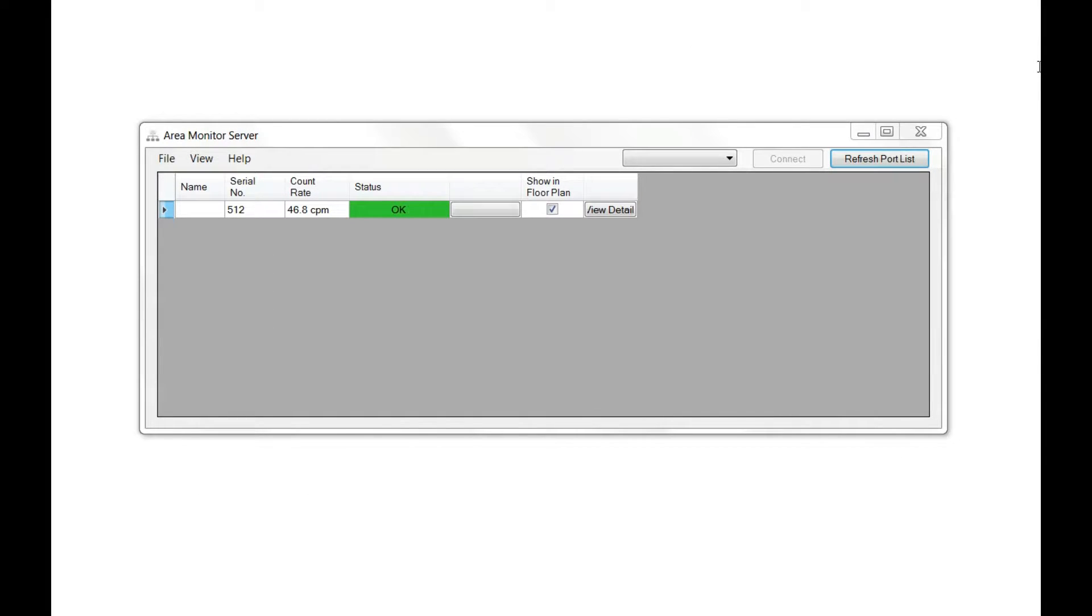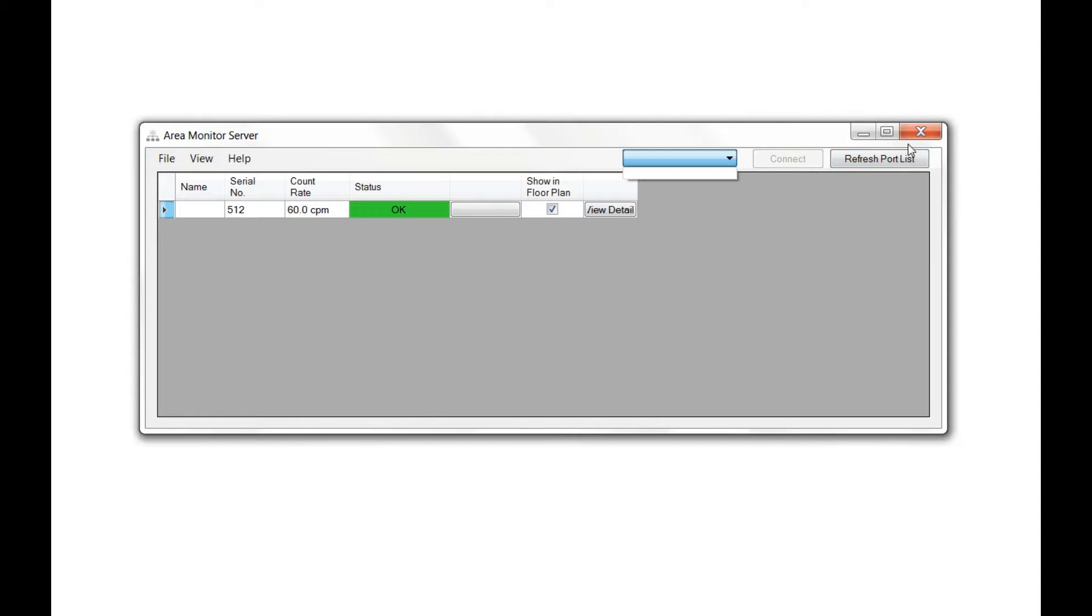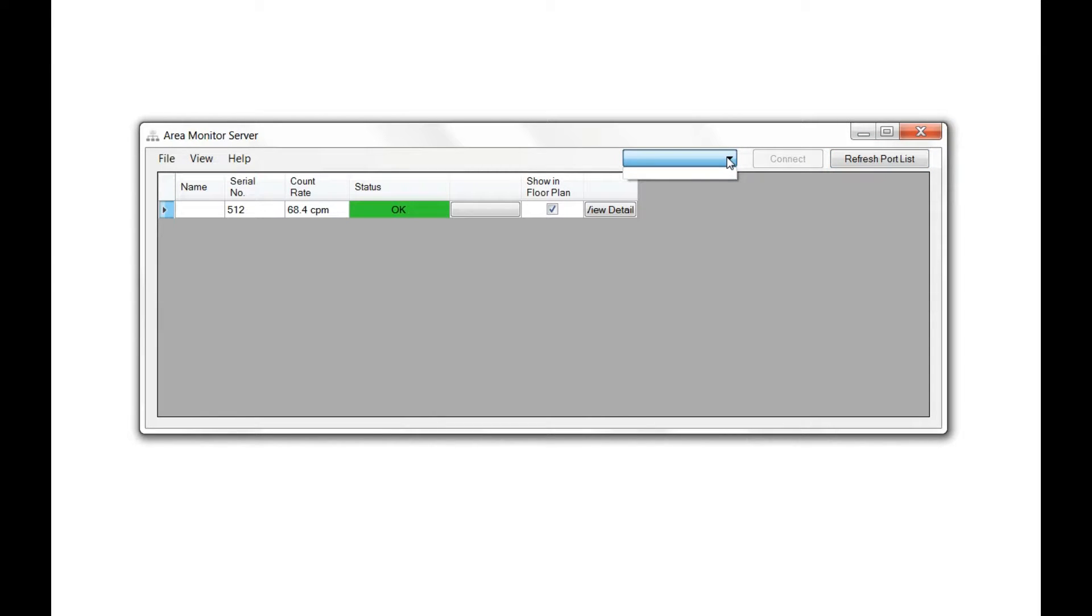To connect via USB, plug your area monitor into your computer. Click Refresh Port List, and a list of COM ports for connecting to your area monitor will be available in the drop-down menu above.